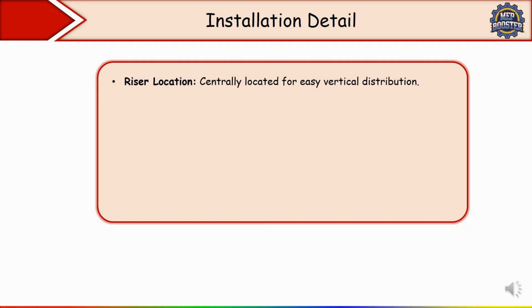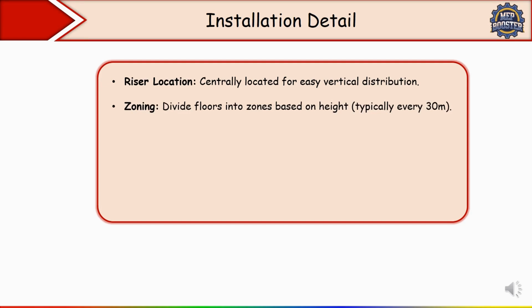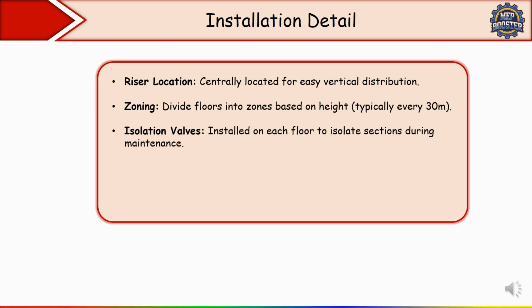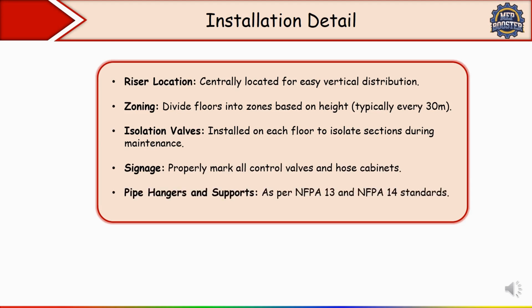So these are the system design requirements. Now we'll see the installation details. Here the riser location is given. Normally the riser location is central for easy vertical distribution. Zoning: here we need to divide the floor into zones based on height, typically every 30 meter. Then an isolation valve is installed on each floor to isolate sections during maintenance. Then properly mark all control valves and hose cabinets, so signage is needed. Then, as per NFPA 13 and NFPA 14 standards, we have to use pipe hangers and supports. So these are the installation details.